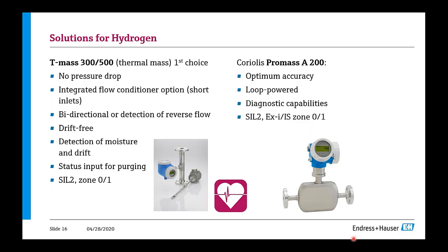So what are the solutions for hydrogen? First, we have the t-mass 300/500. As I mentioned, it's the first choice. This is this future device. It's coming later this year. We are only a few weeks or months away from the release. The beauty is you don't get any pressure drop with these. You have an integrated flow conditioner option here with short inlets. This flange meter comes with a flow conditioner welded in. And when it comes to a bidirectional solution, you have the flow conditioner on both sides, to get short inlet runs. We can even shorten the inlet runs to 2 DN, with an increased uncertainty, however. This is not a problem.